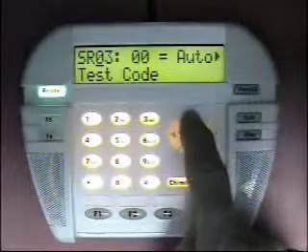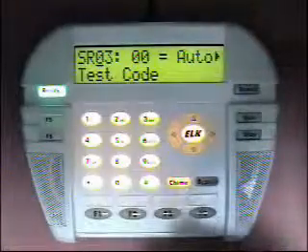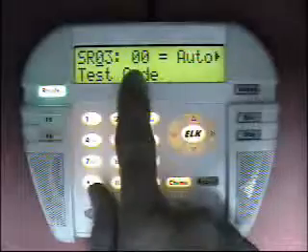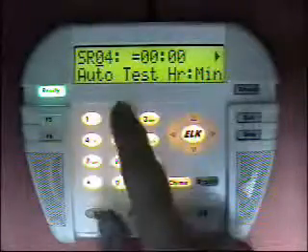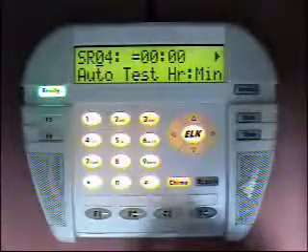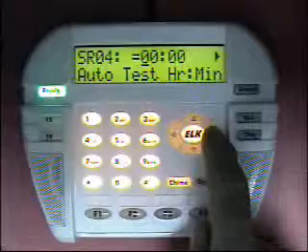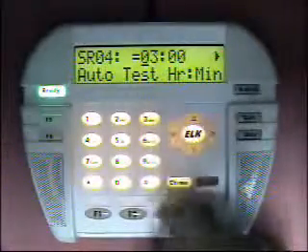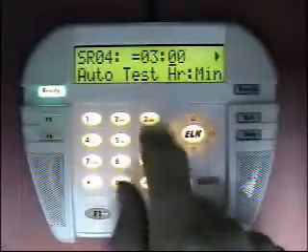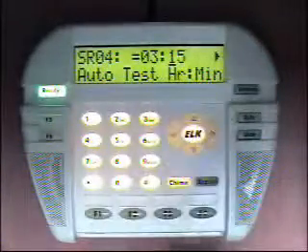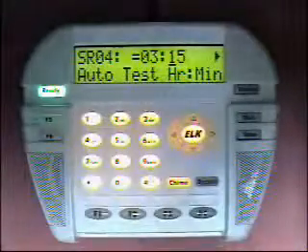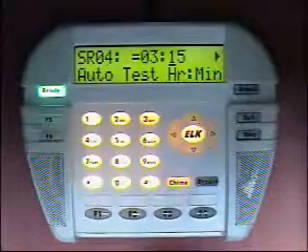The next option is the automatic test code — the code sent to the central station. For SIA and contact ID, this must be set to a non-zero value. The next option is the automatic test time in hours and minutes. 0000 means 12 midnight, using 24-hour military time. For example, to send a test at 3:15 AM, enter 03 for hours and 15 for minutes — at 03:15 in the morning it will send the automatic test to the central station.